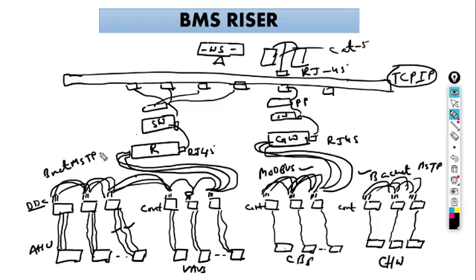One confusion I want to make clear here: why in case of BACnet MS/TP do we only use a router, and we don't use gateways? Because suppose in this facility the whole BMS system is from Honeywell. So in the TCP/IP cloud, in the core switch, one layer is embedded, BACnet over IP, Building Automation Control Network over Internet Protocol. One layer is already embedded. So here BACnet MS/TP, here BACnet IP. So we don't use a gateway. From BACnet MS/TP to IP, we only use routers.